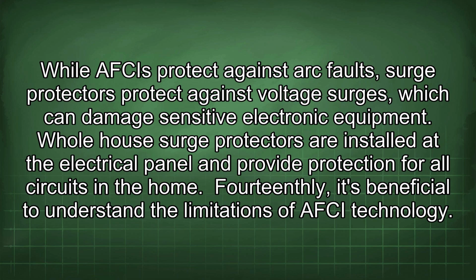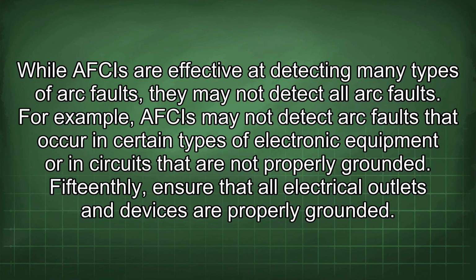14thly, it's beneficial to understand the limitations of AFCI technology. While AFCIs are effective at detecting many types of arc faults, they may not detect all arc faults. For example, AFCIs may not detect arc faults that occur in certain types of electronic equipment or in circuits that are not properly grounded. 15thly, ensure that all electrical outlets and devices are properly grounded.